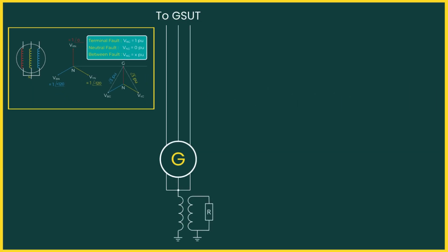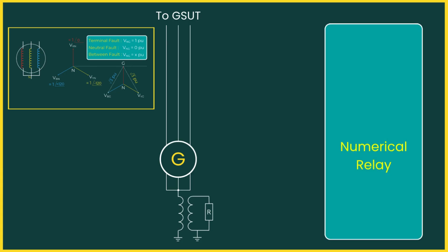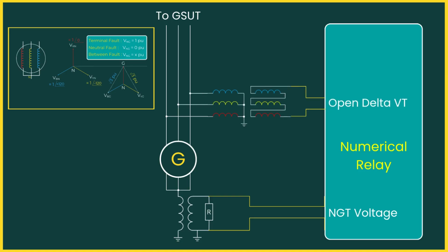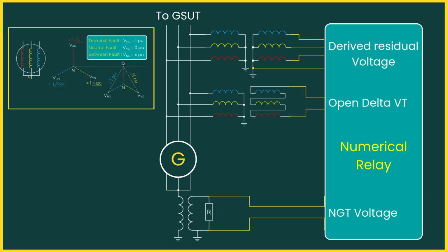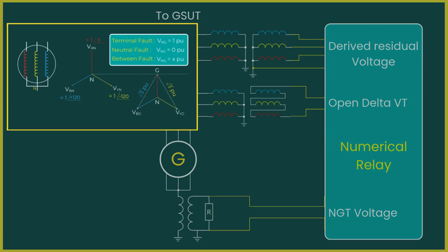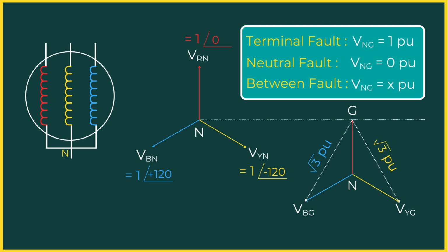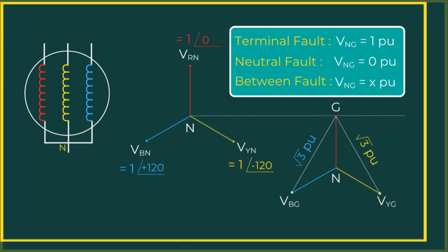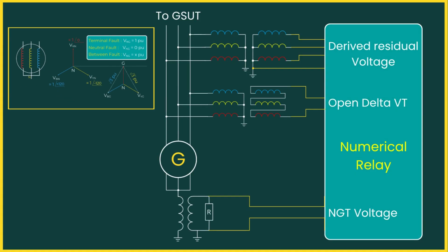There are three practical methods to detect this neutral voltage displacement. Across the neutral grounding transformer, NGT. Across the open delta VT. As derived residual voltage inside the numerical relay. All three methods sense the same fundamental shift, the neutral point moving away from ground potential, but do so using slightly different measurement techniques. In all cases, the displacement voltage detected by the protection relay is of fundamental frequency, 50 Hz or 60 Hz. Let's explore the methods one by one.